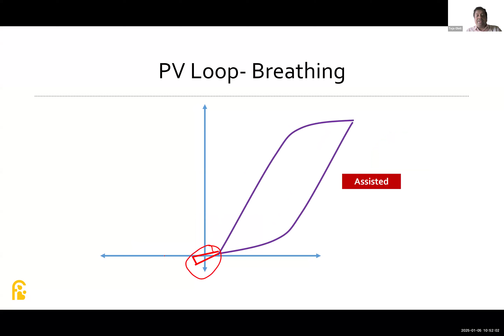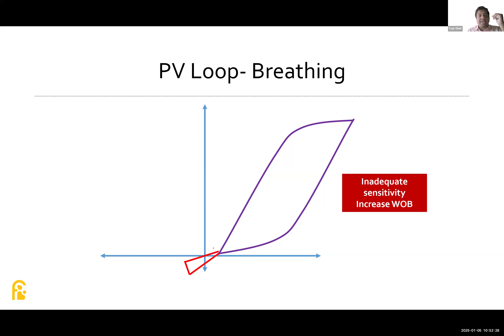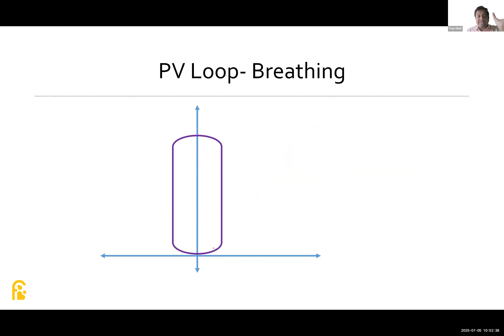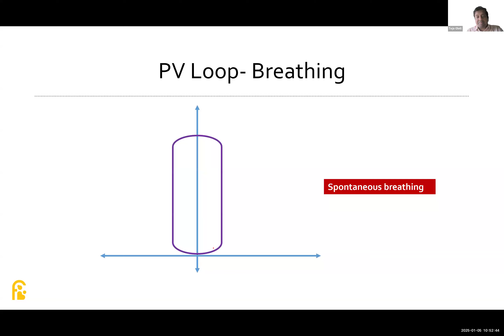Okay. Just based on this tail, you will be able to see whether your trigger is good or not. If the tail is very long, that means that you have kept the trigger at a very high level and it is very inadequate sensitivity. You kept the trigger at very inadequate sensitivity. It can increase the work of breathing. Please look at that baby once again. In a spontaneous breath, it will appear like a figure which is vertical. Okay, because the baby will be having the breathing like this, the spontaneous breath.